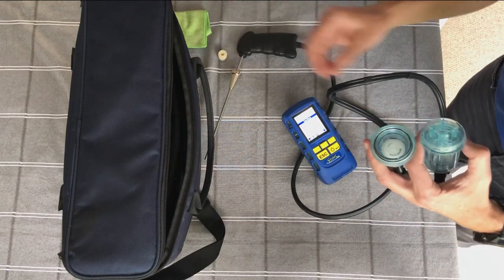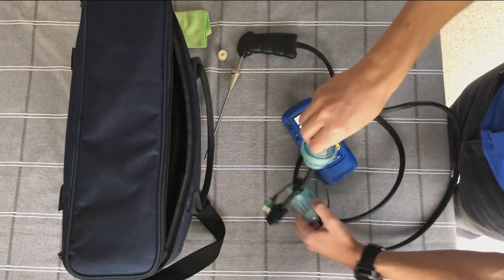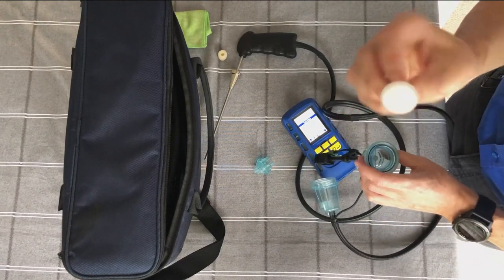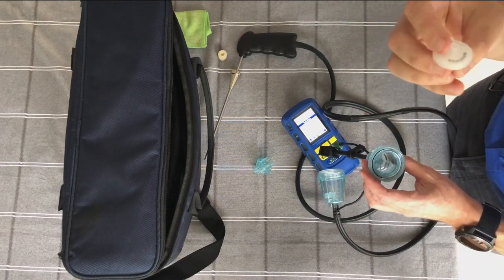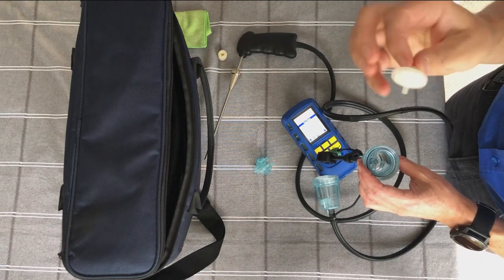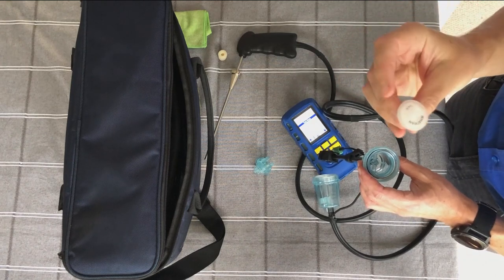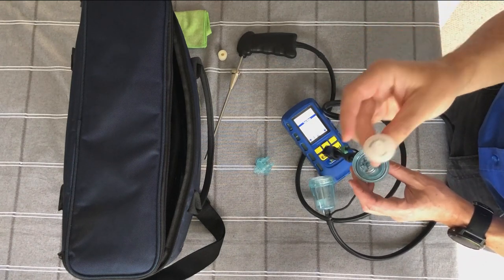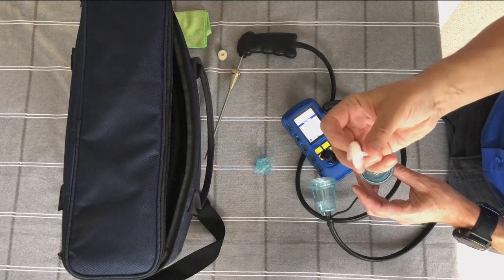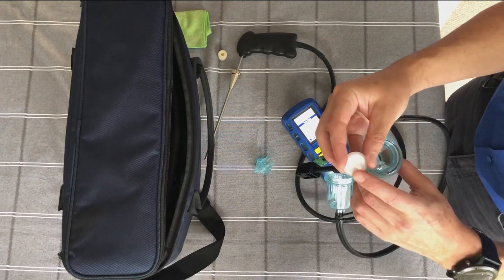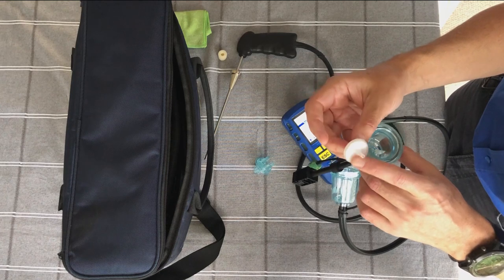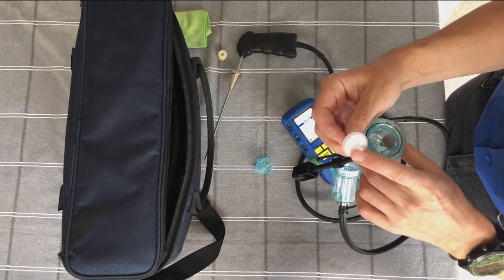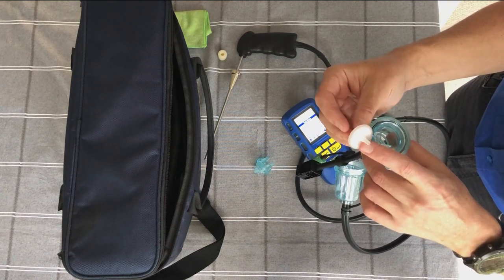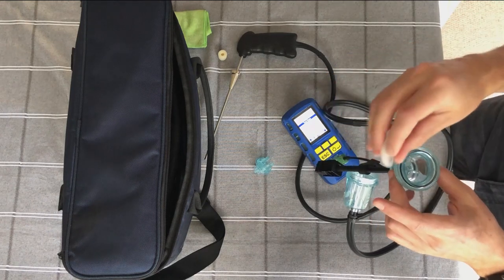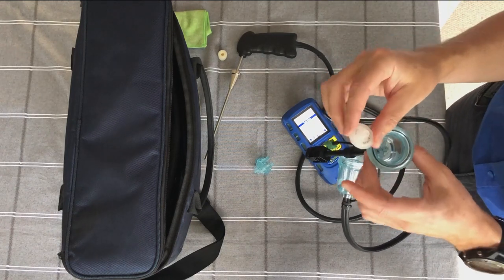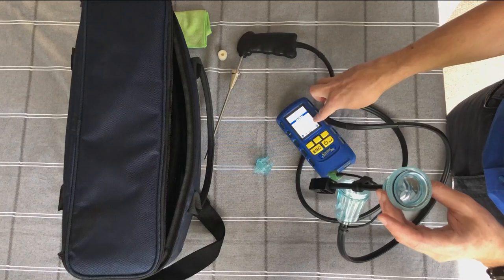The other thing to note is this filter here. This is a really clever and important filter. You've got to have it in place when you're using it. This is a hydrophobic filter, and that long word basically means it's a water barrier. It doesn't let water past this disc. So effectively, as soon as any water moisture droplets touch this, it looks like a filter paper, but it's basically a gauze. It blocks itself so no air can pass through it, and it basically stalls the pump.